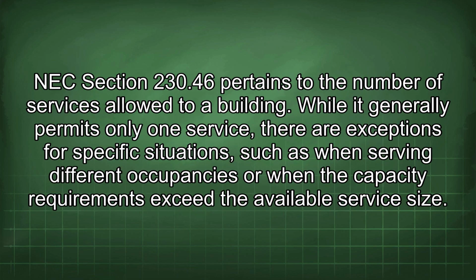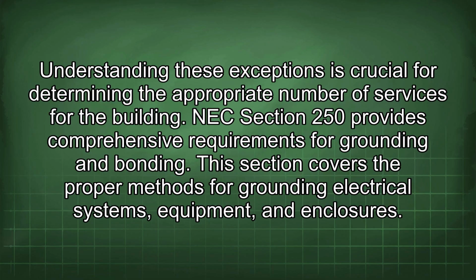NEC Section 230.46 pertains to the number of services allowed to a building. While it generally permits only one service, there are exceptions for specific situations, such as when serving different occupancies or when the capacity requirements exceed the available service size. Understanding these exceptions is crucial for determining the appropriate number of services for the building.